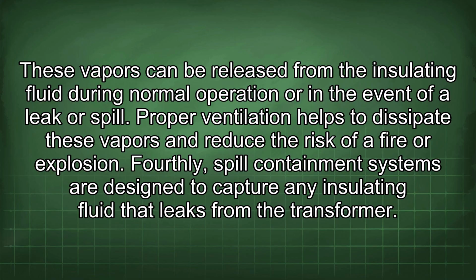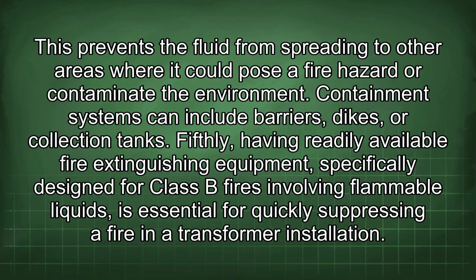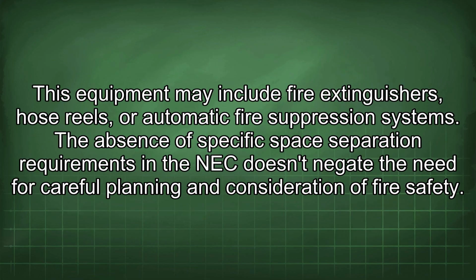Fourthly, spill containment systems are designed to capture any insulating fluid that leaks from the transformer. This prevents the fluid from spreading to other areas where it could pose a fire hazard or contaminate the environment. Containment systems can include barriers, dikes, or collection tanks. Fifthly, having readily available fire extinguishing equipment, specifically designed for Class B fires involving flammable liquids, is essential for quickly suppressing a fire in a transformer installation. This equipment may include fire extinguishers, hose reels, or automatic fire suppression systems.